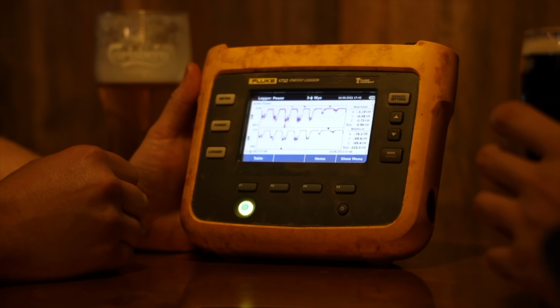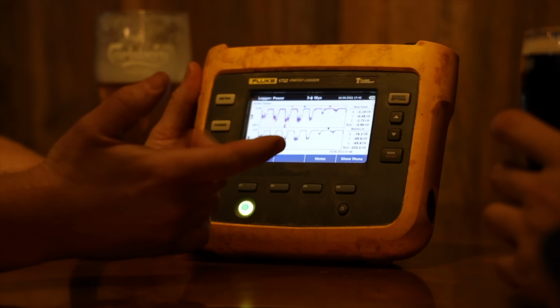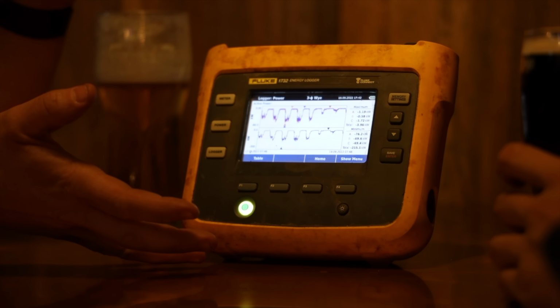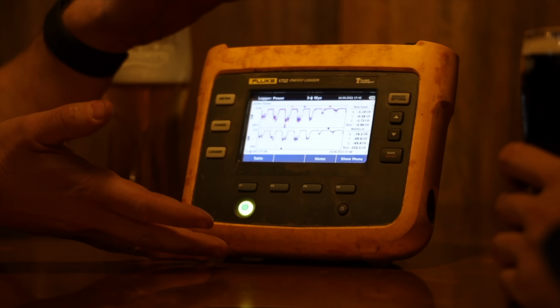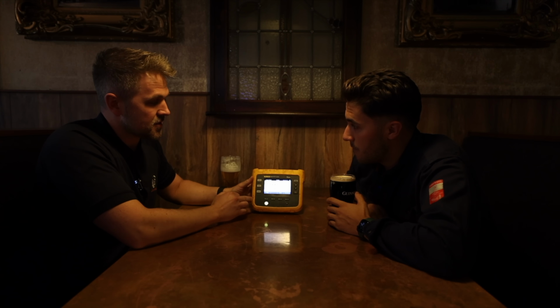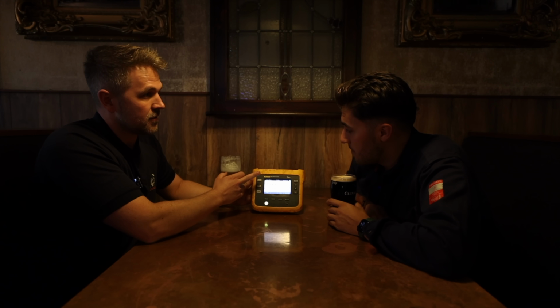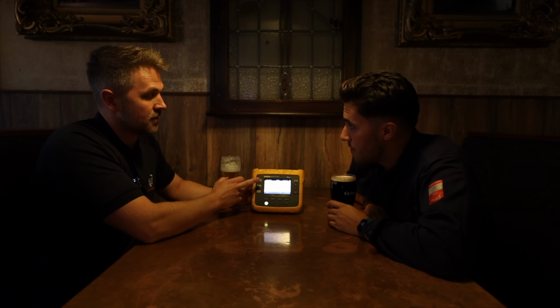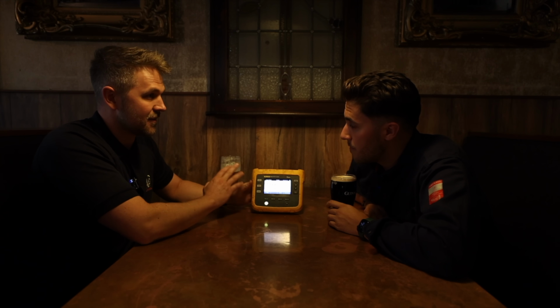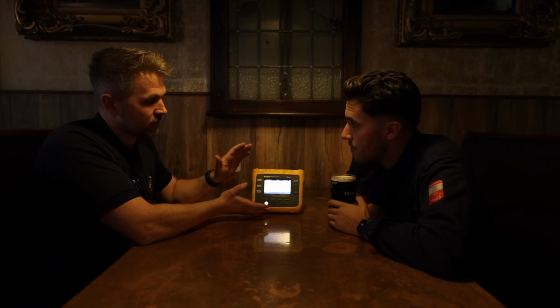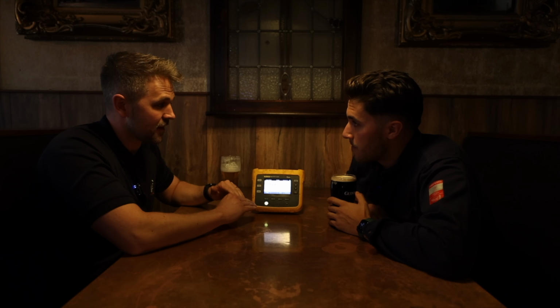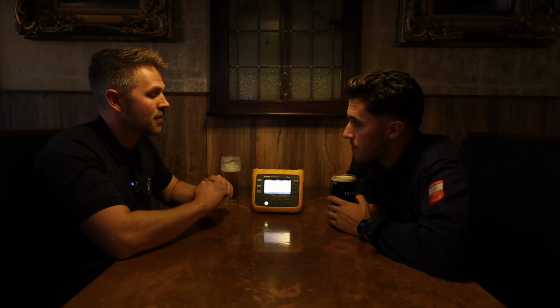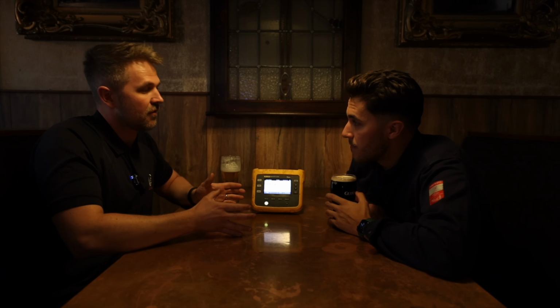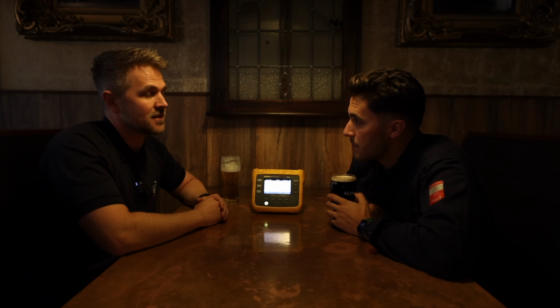Why do you use it? Okay, so this is the Fluke Energy Logger. What this does is analyze all the energy being used in that building. It gives you your kilowatt hours, your kilowatts, your KVAR, your power factor. It gives you everything. We've done this one over a 7-day period, and basically it gives you what time of day it's been used, the maximum, the minimum. It gives us a full picture of what the power usage is in the building.